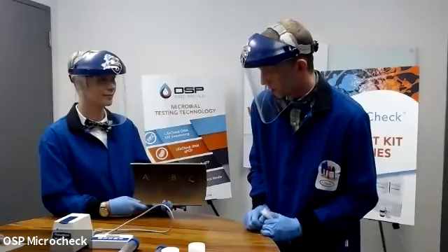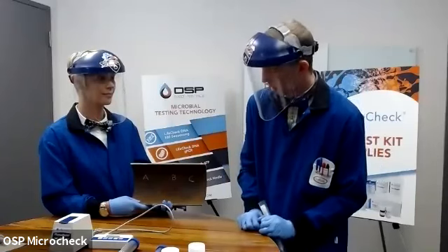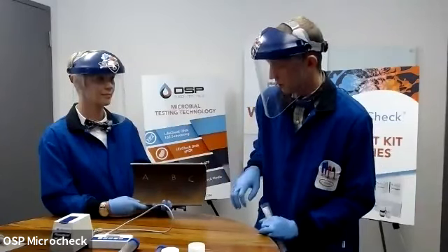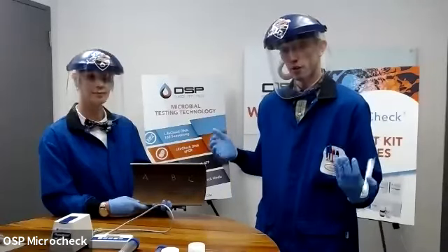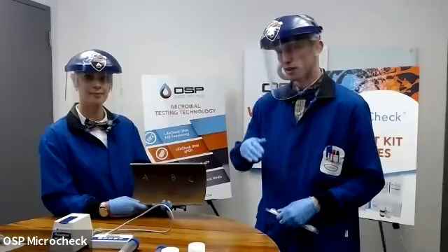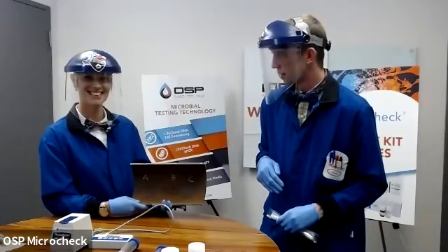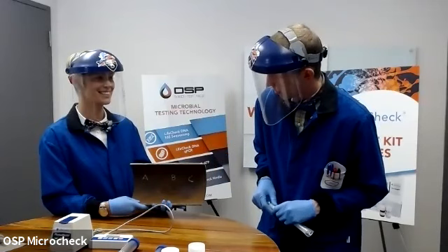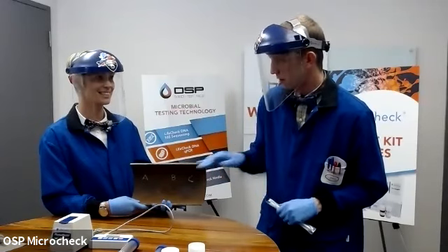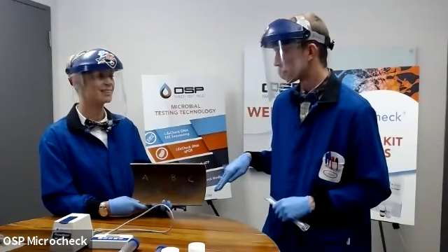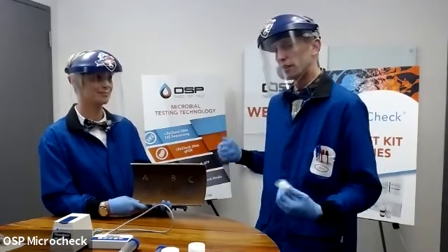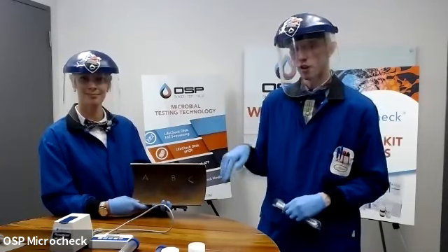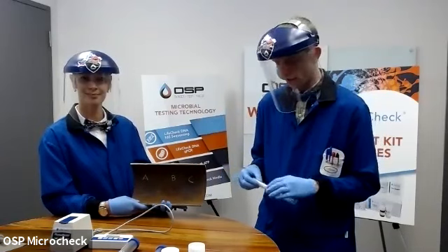And the client question was, of course, could microbiology be a part of that? And from a microbiologically influenced corrosion perspective, the presence of microbes alone, which is what ATP testing is going to test for, is not by any means sole evidence that MIC is occurring, but it is at least a first step into understanding if there's even microbes present within that pit as compared to the parent surface. And then, of course, we can complement that with our DNA testing technology to see if the types of microbes that are able to influence MIC are there.